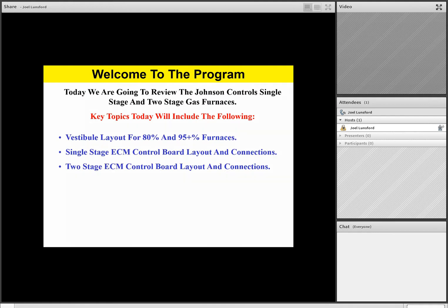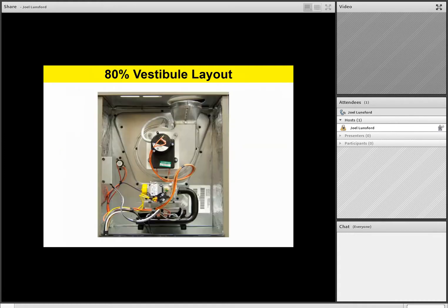Today we're going to be going over the Johnson Controls single-stage and two-stage gas furnaces, and some of the key topics that we will be talking about today are as follows. We're going to look at the vestibule layout for 80% as well as 95% furnaces. We're going to be talking about single-stage ECM motor control board layout and connections, two-stage ECM control board layout, and 24-volt connections. Now remember, on some products, they are communicating capable. However, on the single-stage ECM and the two-stage ECM control boards, they will be 24-volt only connection.